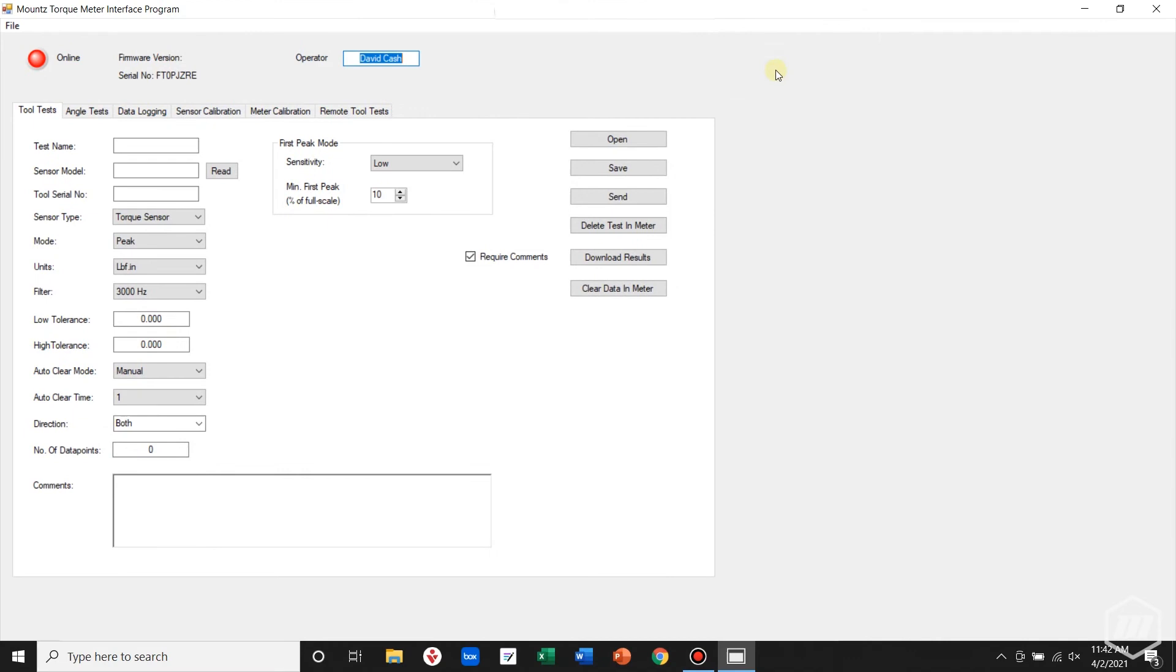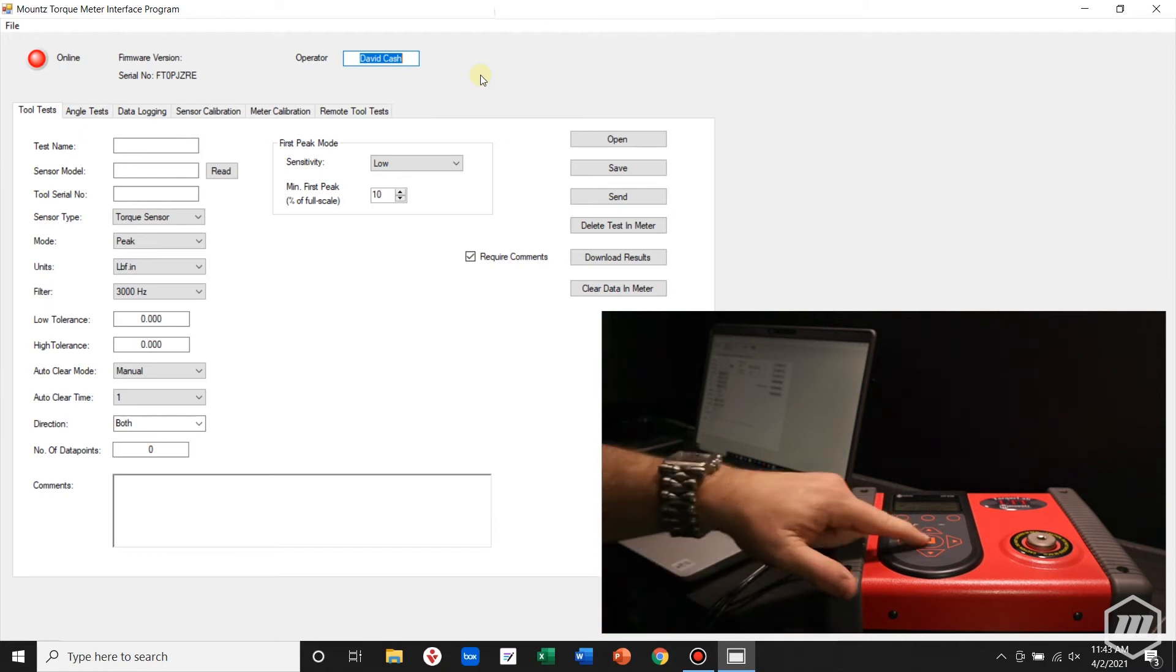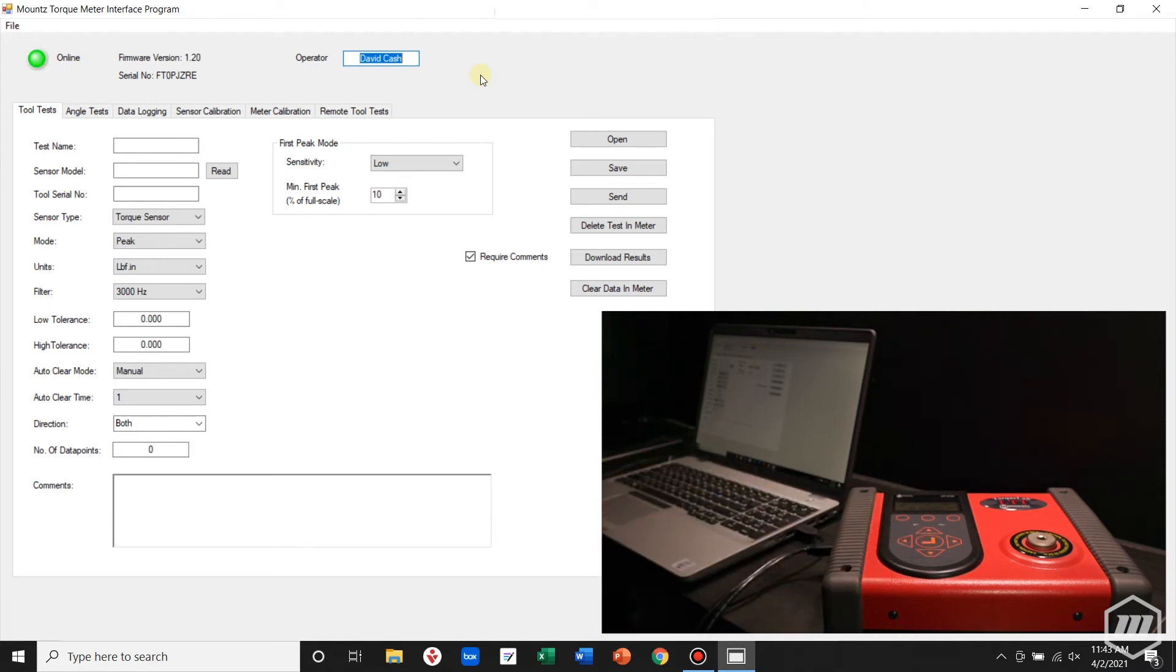With the torque interface program open, you can tell if we are connected via the light indicator in the upper left. Attach your LTT analyzer and power it on. The status light should change to green.